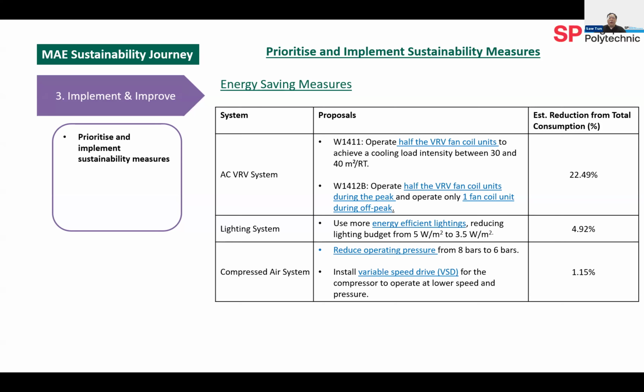For the W1411, we try to operate half of the VRV fan coil units to stretch our cooling load intensity from 18 meters square per RT to around 30 to 40 meters square per RT. Similarly, for the W1412, we also only operate half of the VRV fan coil units during peak periods and only one fan coil unit during off-peak periods. For the compressed air system, we changed the operational pressure from 8 bars to 6 bars.